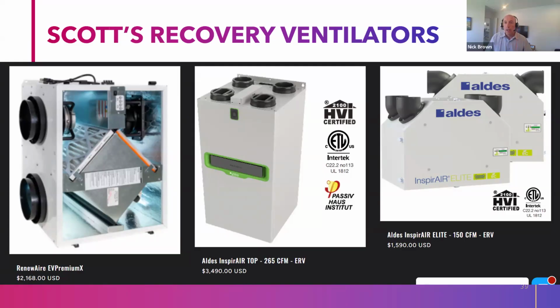Fans are much more efficient at half speed, aren't they? They are much more efficient, and it's not only the efficiency and the burnout of the motor, but then you have capacity for boost. As soon as you need to boost and it's rated 150 but you're already running it at 150, you've got no boost. But if you're running it at 85 out of 150, you can boost that and get maybe 60 minutes of boost, getting more ventilation into the home.